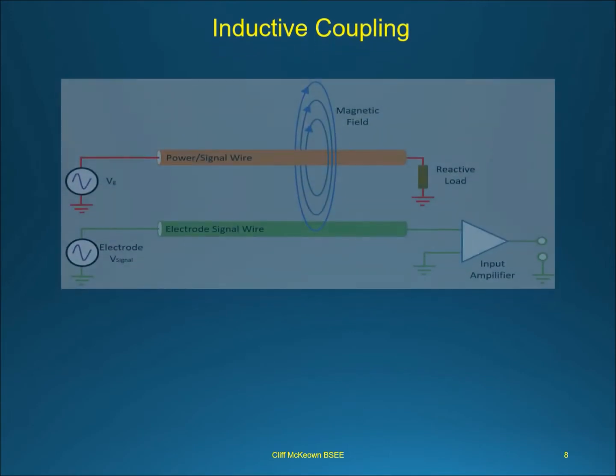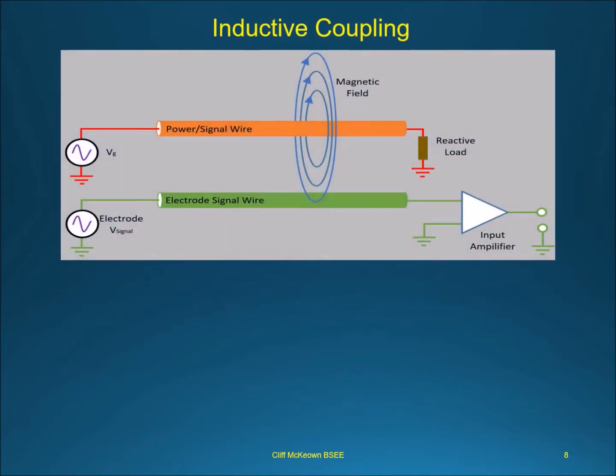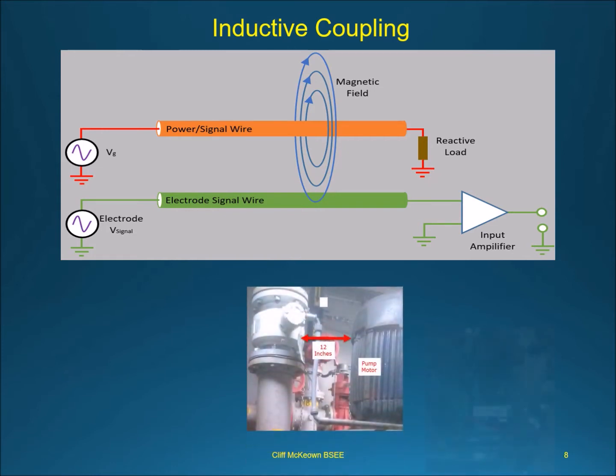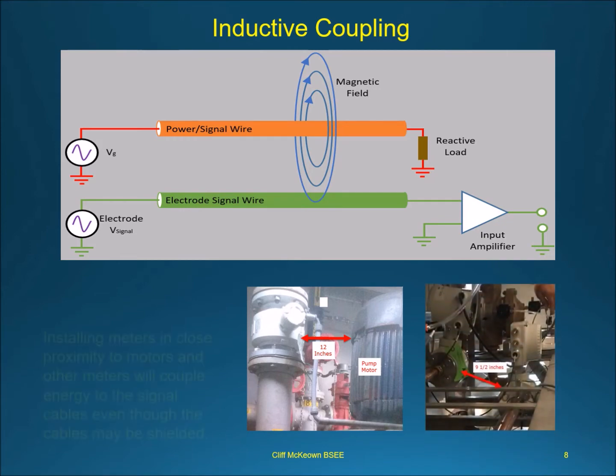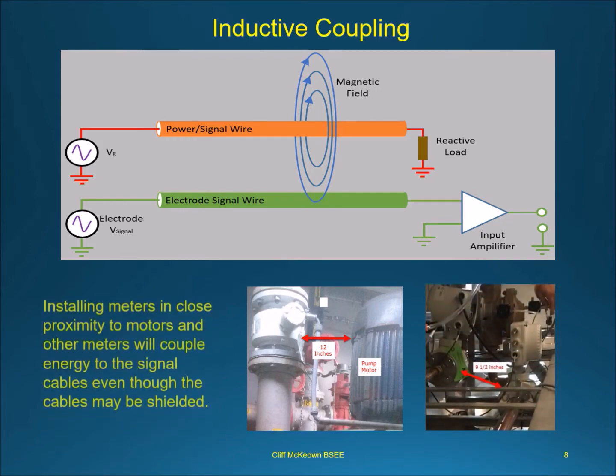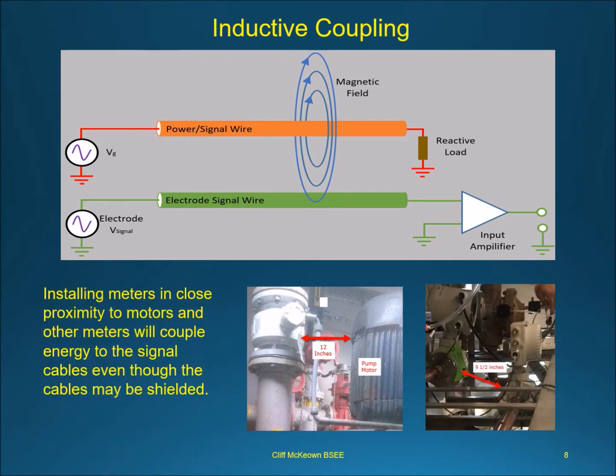Installing meters in close proximity to motors and other meters will couple energy to the signal cables even though the cables may be shielded. Cable shields do not completely block EMI but simply mitigate it. Again, distance from the source is a key factor here, since the further away from the source, the weaker the EMI.